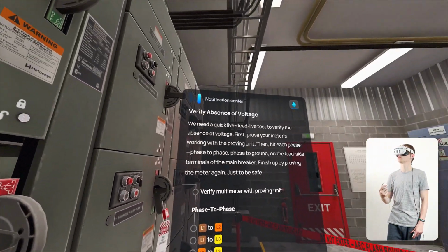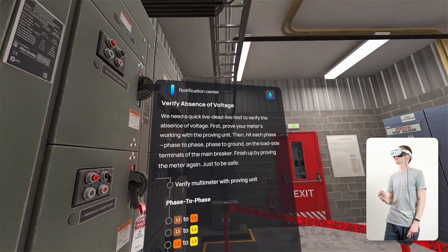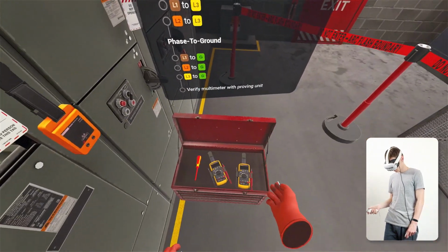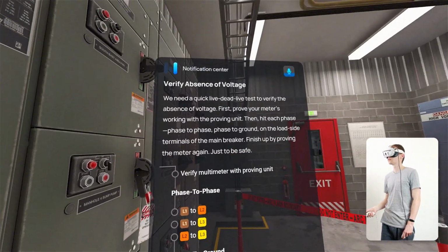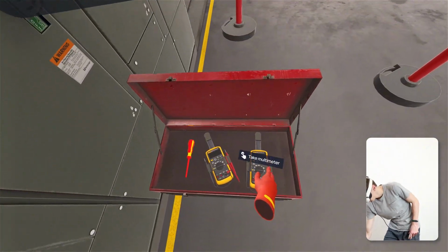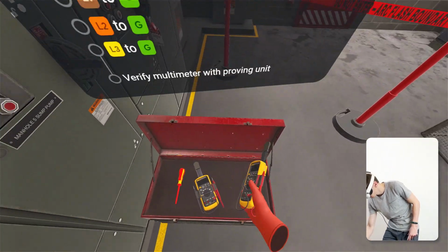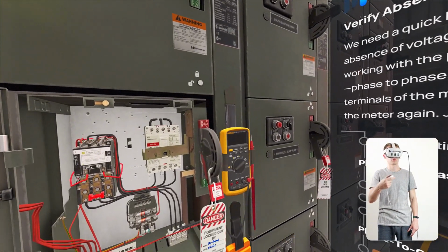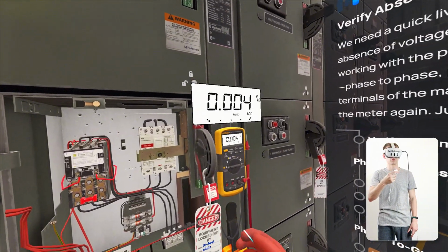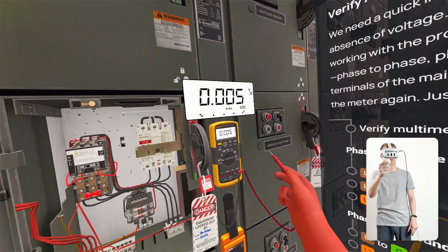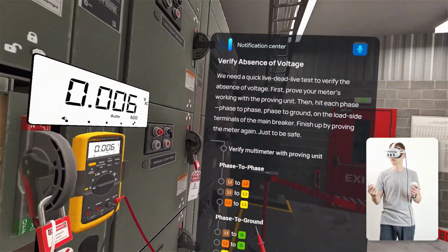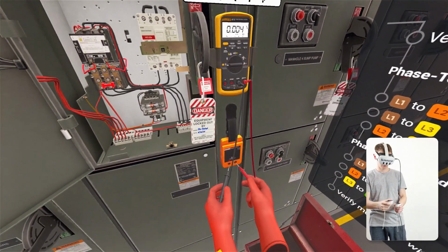Got your multimeter? We need a quick live-dead-live test to verify the absence of voltage. First, prove your meter's working with the proving unit. Then, hit each phase, phase to phase, phase to ground, on the load side terminals of the main breaker. Finish up by proving the meter again, just to be safe. Over.